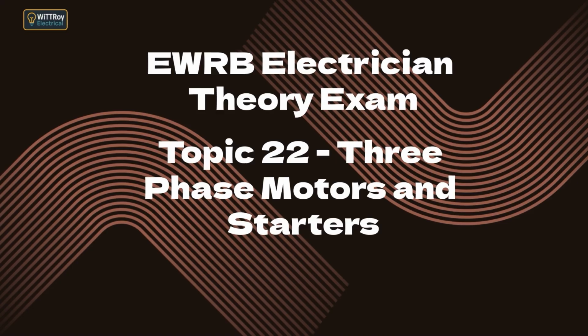2. Auto-transformer starter. Operation: uses a tapped auto-transformer to supply the motor with a reduced voltage during start. After acceleration, the motor is switched to full line voltage. Advantages: best reduction in starting current compared to other methods, higher starting torque than star-delta. Disadvantages: more expensive and bulky, more complex wiring. Applications: large motors that require higher starting torque, compressors, crushers.